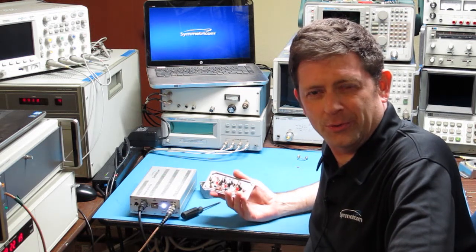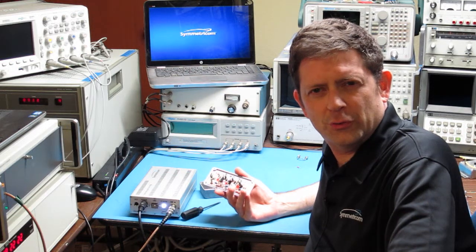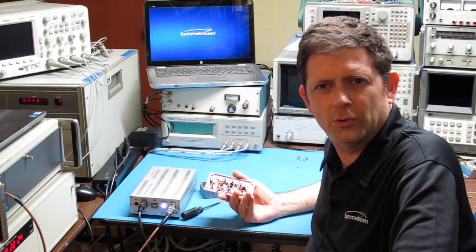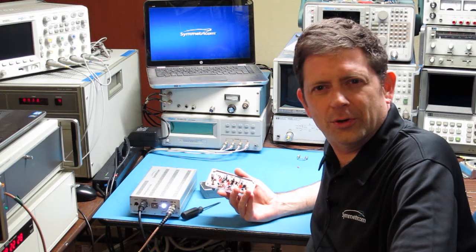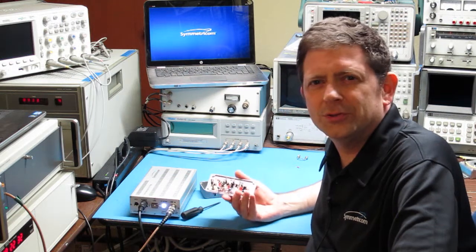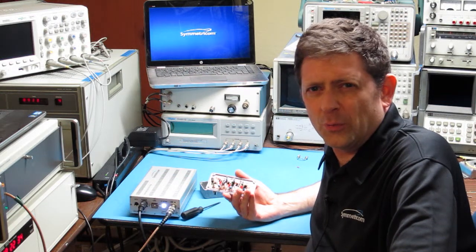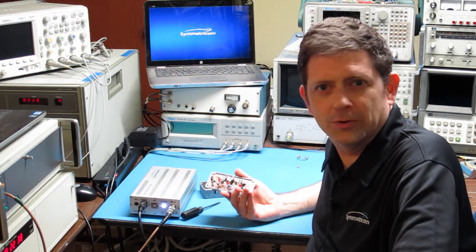Most of our other demos have emphasized the use of the 3120A to measure the short-term noise and long-term stability of an oscillator or a frequency standard of some kind, so I thought I'd take a few minutes to show you a different application. You can use the 3120A to measure the stability of two-port devices, not just signal sources.